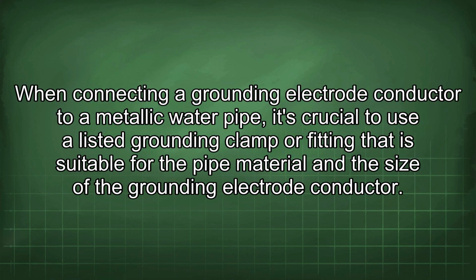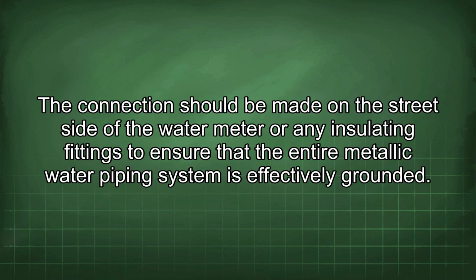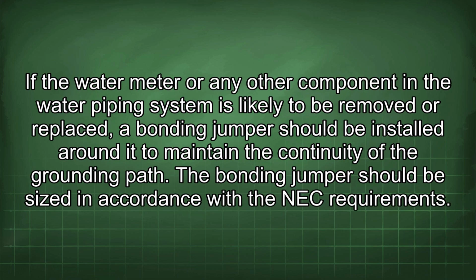When connecting a grounding electrode conductor to a metallic water pipe, it's crucial to use a listed grounding clamp or fitting that is suitable for the pipe material and the size of the grounding electrode conductor. The connection should be made on the street side of the water meter or any insulating fittings to ensure that the entire metallic water piping system is effectively grounded. If the water meter or any other component in the water piping system is likely to be removed or replaced, a bonding jumper should be installed around it to maintain the continuity of the grounding path. The bonding jumper should be sized in accordance with the NEC requirements.